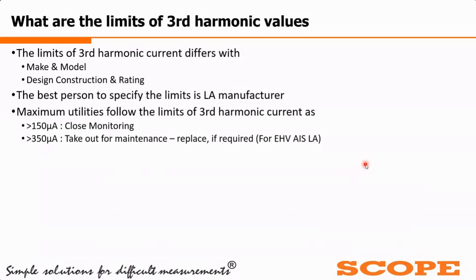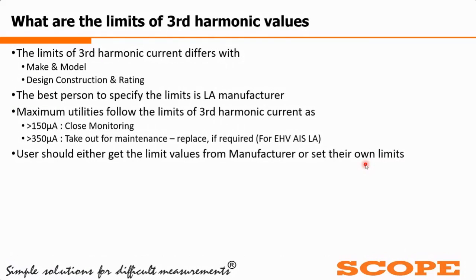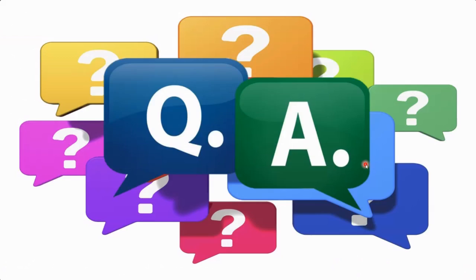They have said that at a limit of 150 microampere and above, they keep the LA under close monitoring. At more than 350 microampere, they take out the LA for maintenance, and if required, they replace it. So either get the limit values from the manufacturer or set your own limit, your own standard. As you have a standard operating procedure in your organization, follow that standard. Whatever standard your organization fixes, follow it. Whatever the LA manufacturer tells you, follow that. This is just a reference scale, nothing else. So with this, from my side, I am done.